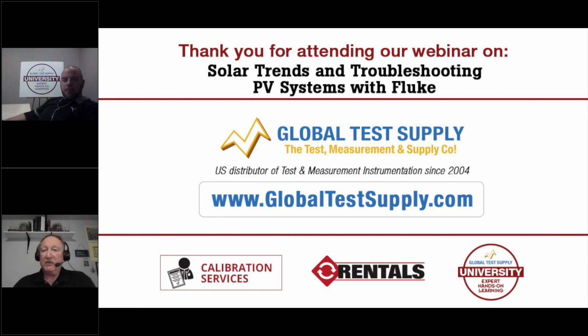That's a really good question, Chris. I think really two to three basic components would help anybody starting into the solar industry. First and foremost, having a good clamp meter, you need to be able to measure voltage and current, because that's how the system is designed, to output DC. Some residential systems actually have little mini inverters on the back of the solar panel, and those all tie in and go into series, but we still need to check that voltage and current. Also, having a good irradiance meter is important, because that helps you analyze if the panel is outputting correctly. You can add thermal imaging later, and add other components as you get more advanced into the solar workflow. But really, a good clamp meter and a good irradiance meter are the key win.